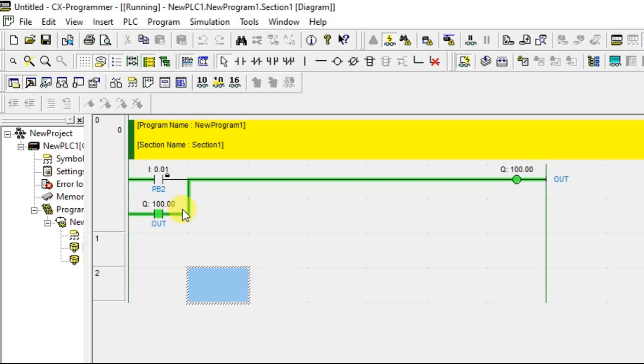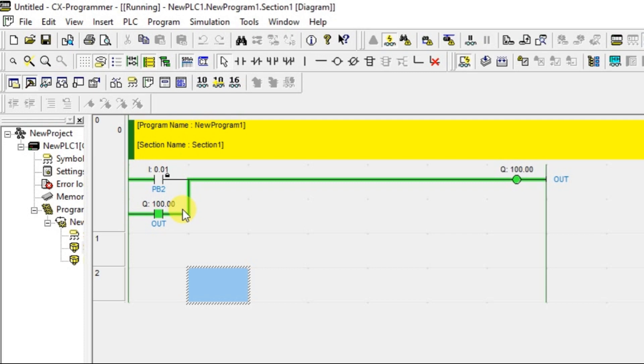This contact is called a latched contact, or seal-in contact. You take the same ID and same address of the output and put that in parallel with the input. Since it is in parallel, even though your main input is off, your output contact will supply power to keep the output coil on. This is called latching.